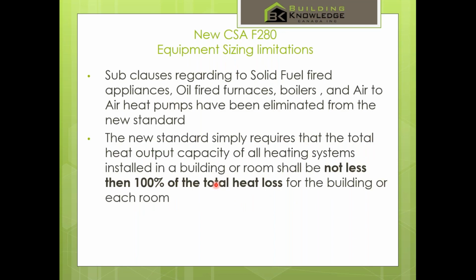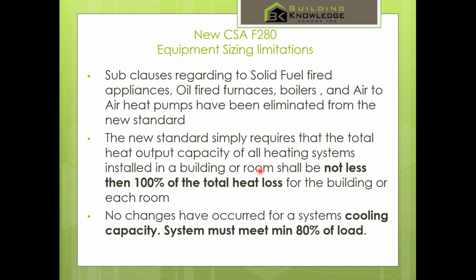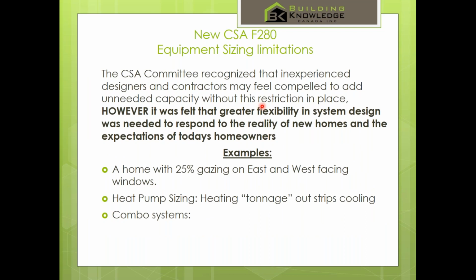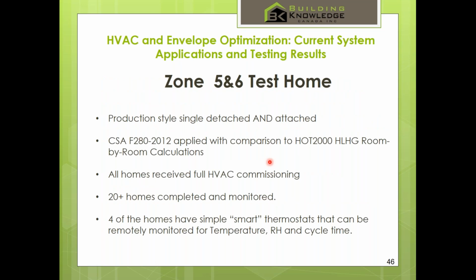Equipment sizing limitations. This is a conundrum. The new CSA standard basically says that a building room shall not be less than 100% of the total heat loss for the building in each room. It no longer has the restriction of you cannot oversize by 40%. And on cooling, it says that it must meet 80% of the load. So this is a bit of a conundrum for some folks that feel strongly about the oversizing issue. And the reason is that the committee felt against, because of a lot of examples, heat pumps, combo systems, window glazing, that they needed to leave the designers some flexibility. They may use equipment that's capable of larger loads, but oversizing may not be an issue because that piece of equipment may be fully modulating, and it might be used for two purposes. It may be used for space heating and for domestic hot water. So again, that's changed.